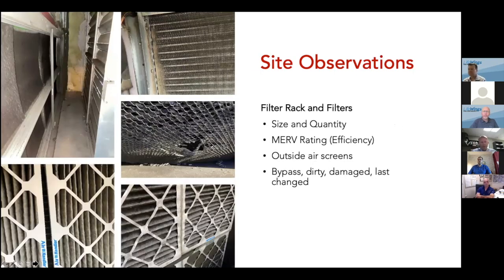So filters. And I didn't even pick the worst case filters, but it's a good sampling of what we found on site. The middle right column is actually an outside air intake. This is very common for rooftop units, especially rooftop units close to salt water. Essentially the mesh grid deteriorates very rapidly in salt laden air. So that is obviously a maintenance issue, and could be repaired.